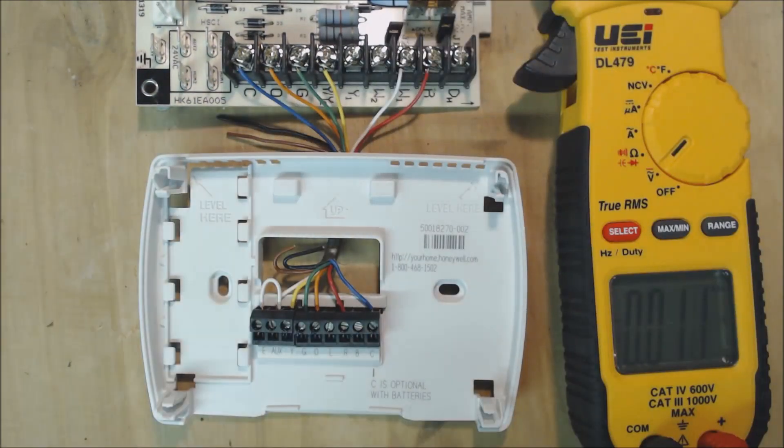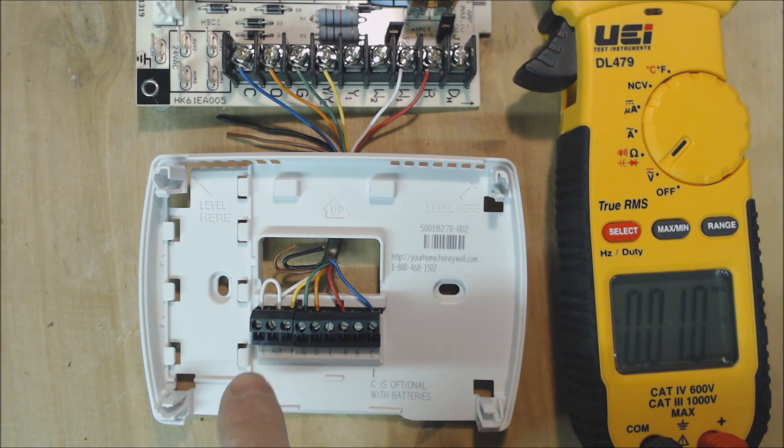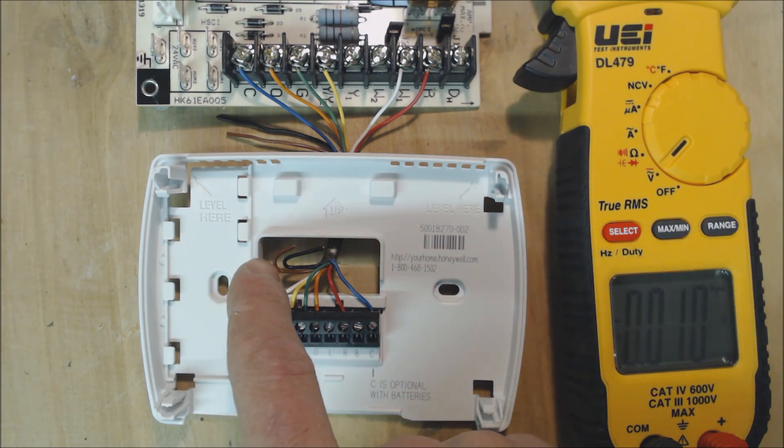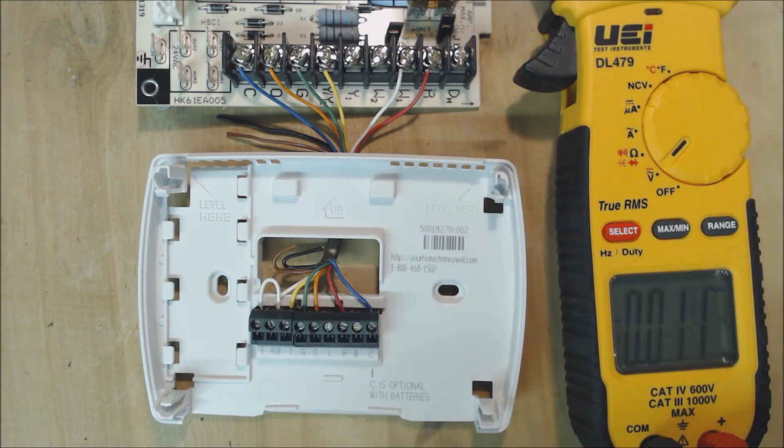Now if we open this thermostat up, you're going to see that we have a jumper between aux and E. If you had three types of heat—say your heat pump for refrigerant heating the house, then auxiliary heat like a hot water coil, and then E meaning electric resistance heat—you could have three types of heat if you pulled that jumper out. But a lot of times this jumper is left in place so that electric resistance turns on anytime aux is called or E is called.